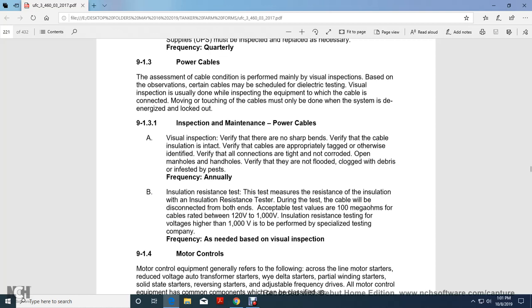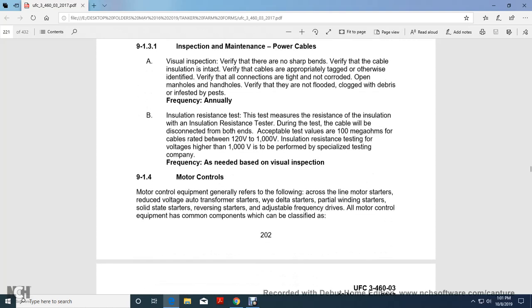Alright, insulation resistance test. This test measures the resistance of the insulation. During the test, the cable will be disconnected at both ends. The acceptable test level is 100 megaohms for cable rated 120 to 1,000 volts. Insulation resistance testing of cable higher than 1,000 volts is performed by a specialized testing company. Frequency is as needed, based on visual inspection.